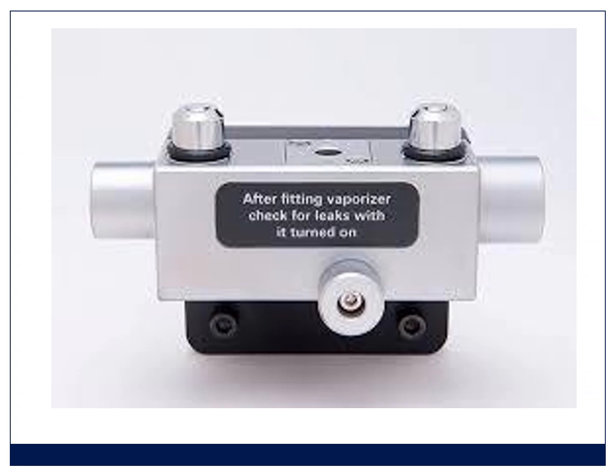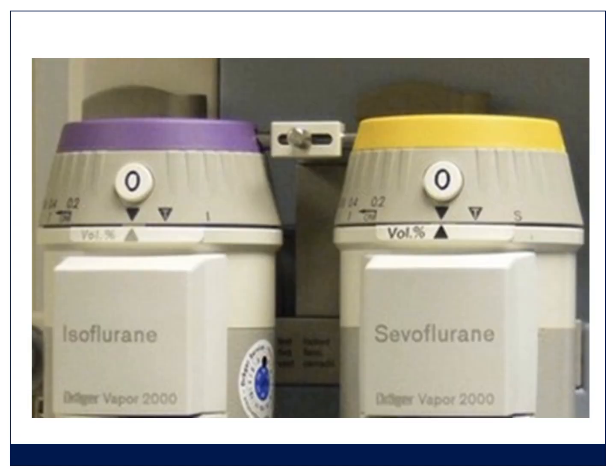For your vaporizers, they sit on a back bar. And I've just put this picture up here to show you that there are O-rings on those back bars. There's an O-ring there. And the vaporizer must be seated securely and locked onto this back bar. And if there's an O-ring missing, you'll find that there's a leak at this point. And it's one of the sources of a leak that we sometimes struggle to find. So they go onto this back bar.